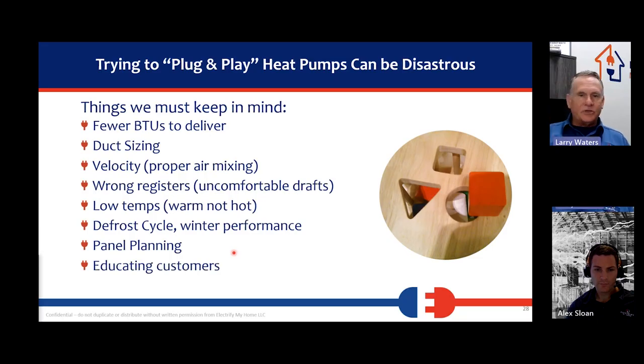Educating customers is super important, and it doesn't get done when we're talking about, hey, I can get this system installed for you next week, and it's a 3-ton system. We're pulling out a 3-ton, and we're going to put in a 3-ton heat pump. When that happens, you don't have time to do a load calc. You don't have time to calculate the ductwork. You don't have time to do any of that. And that's the way the industry is going. We need to get away from that when we're converting to heat pumps.